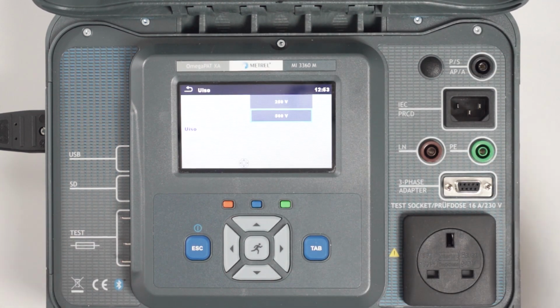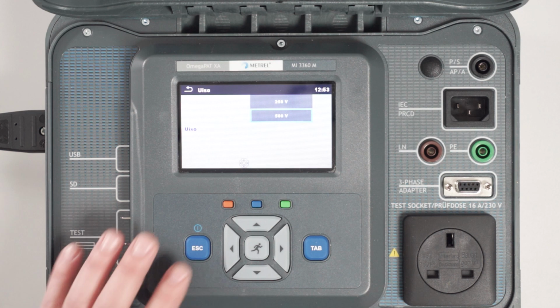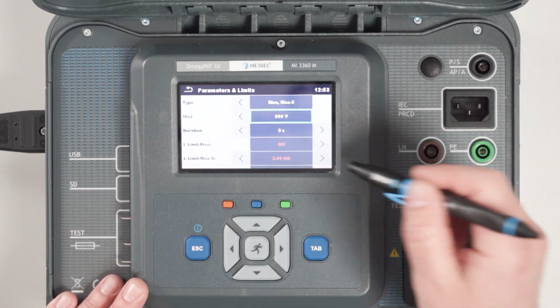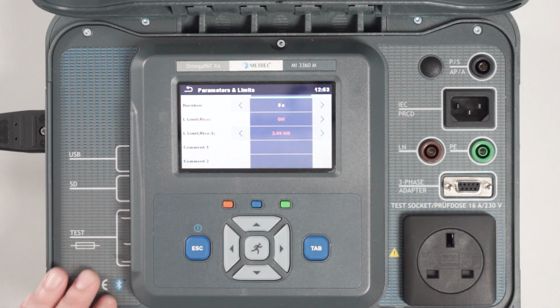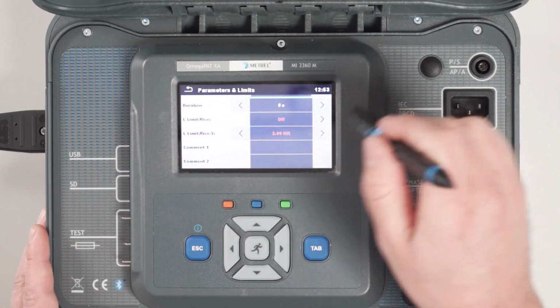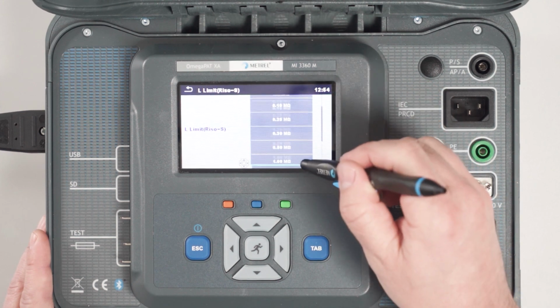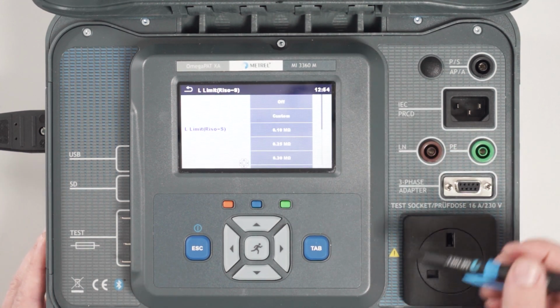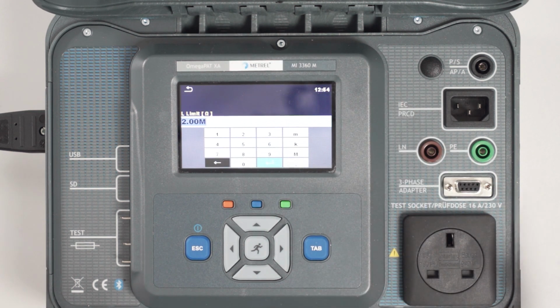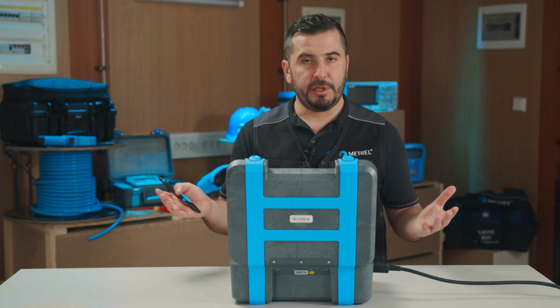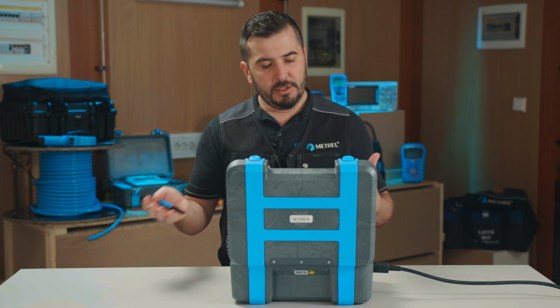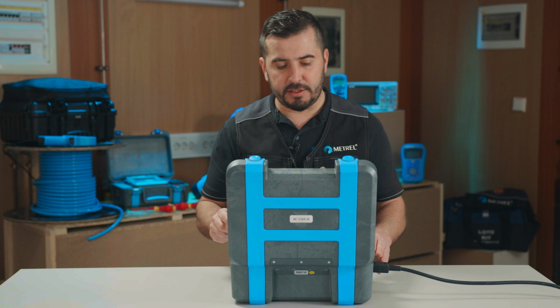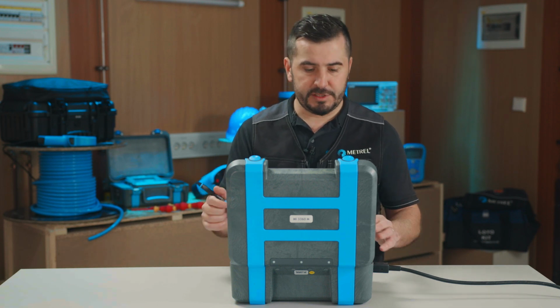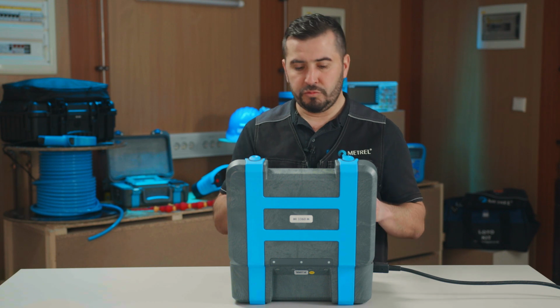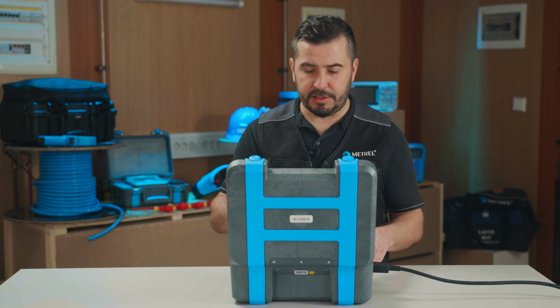We can choose different parameters such as different voltages or different currents for the earth continuity test, and then duration and limits. What's nice about this device is that for all limits we have a predefined list of limits available, but we can always enter our own custom limit if needed. Meaning, if there are some changes in the code of practice or other standards, we always have the possibility to enter our own custom limit.